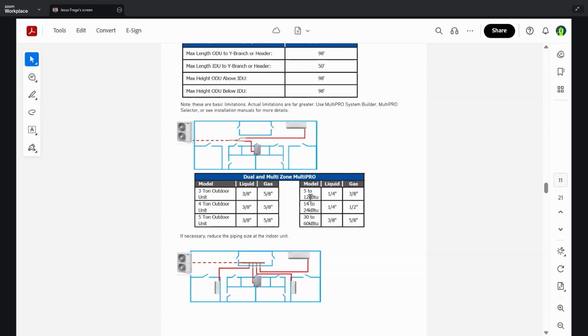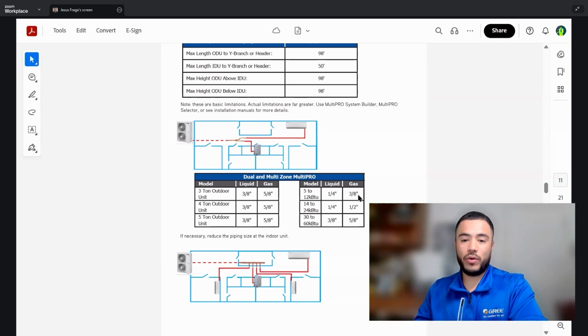So now we have 5 through 12 will be 1/4 to 3/8 gas and liquid, and 14 through 24 will be 1/4 to 1/2 gas and liquid. 30 to 60 is 3/8 to 5/8 gas and liquid.